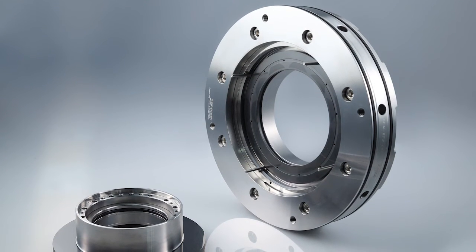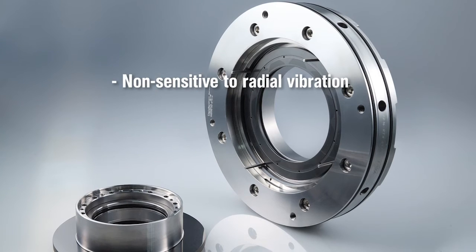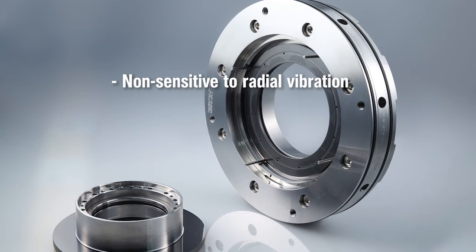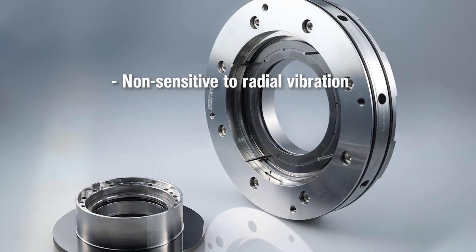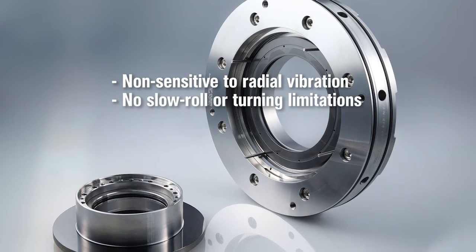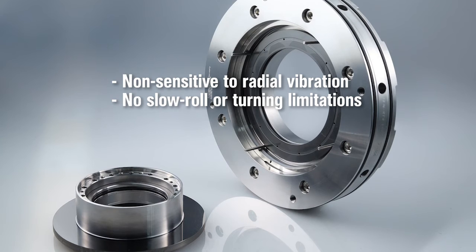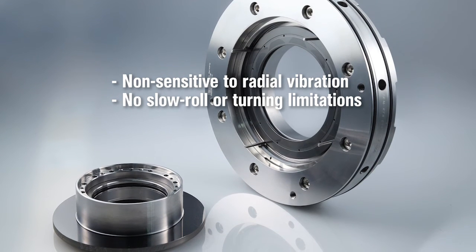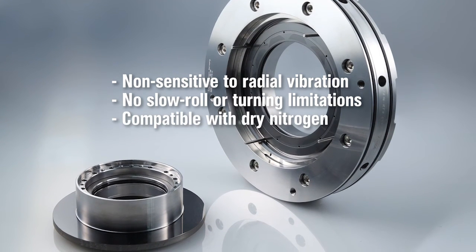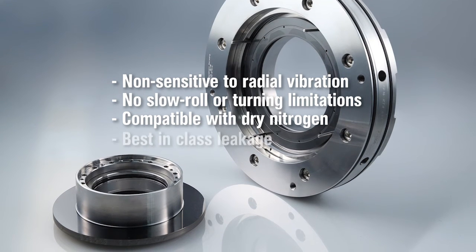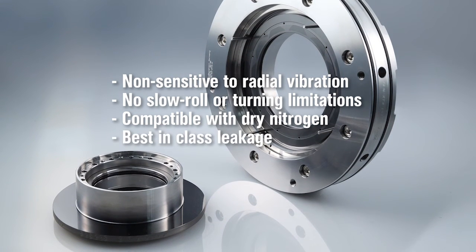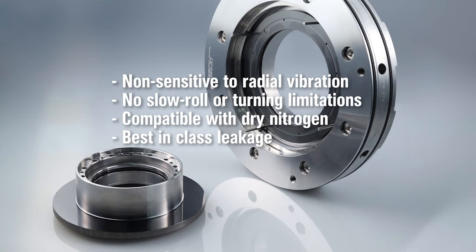Further advantages of the COBA seal: it is non-sensitive to radial vibrations due to the axial sealing gap. There are no limits regarding slow roll or turning operation due to the static lift-off. There are no limits regarding the dew point of the separation gas, and it has lower nitrogen consumption than any other system.